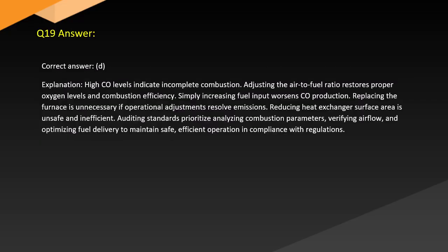Answer. Correct answer. D. Explanation. High CO levels indicate incomplete combustion. Adjusting the air-to-fuel ratio restores proper oxygen levels and combustion efficiency. Simply increasing fuel input worsens CO production. Replacing the furnace is unnecessary if operational adjustments resolve emissions. Reducing heat exchanger surface area is unsafe and inefficient. Auditing standards prioritize analyzing combustion parameters, verifying airflow, and optimizing fuel delivery to maintain safe, efficient operation in compliance with regulations.